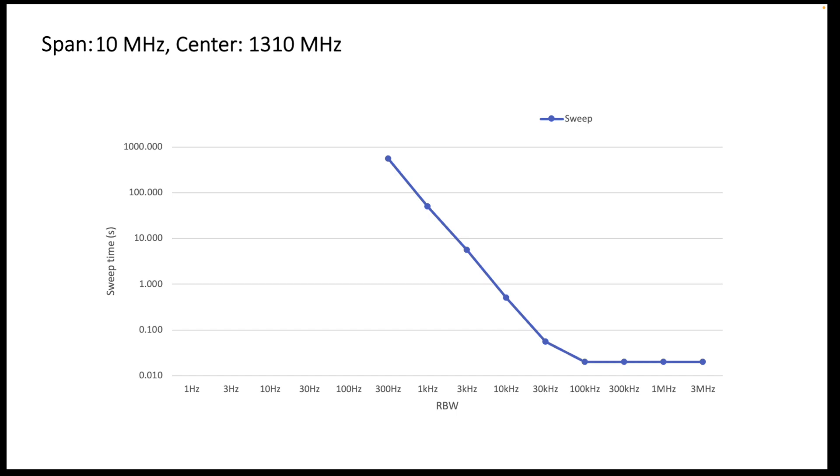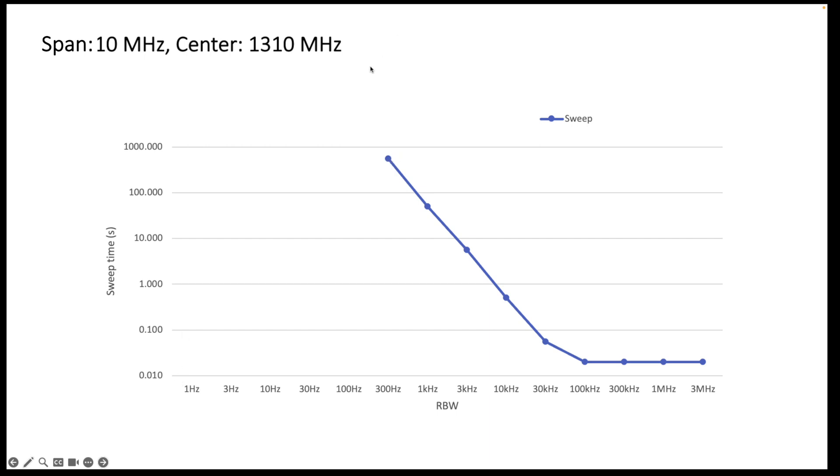Now these differences in time are so big that I actually will display them here in a logarithmic vertical scale here, so we get a bit more sense for the relationship between the resolution bandwidth and the time it takes to do a sweep. So as you can see here again on this graph, I'm presenting the same data.